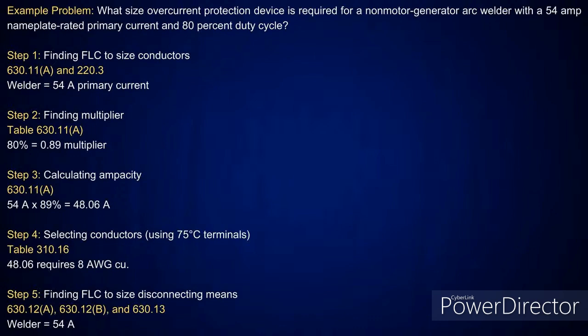So this, once again, and think about what I'm saying here, it's just like the AC unit. That is what? An assembly. It comes as one unit. So you're going to use the nameplate value here. In this case, I've got a non-motor generator arc welder. It's 54 amps and it has an 80% duty cycle. So the first portion, step 1, get your amperage. That's what we always do. So we know it's 54 amps.